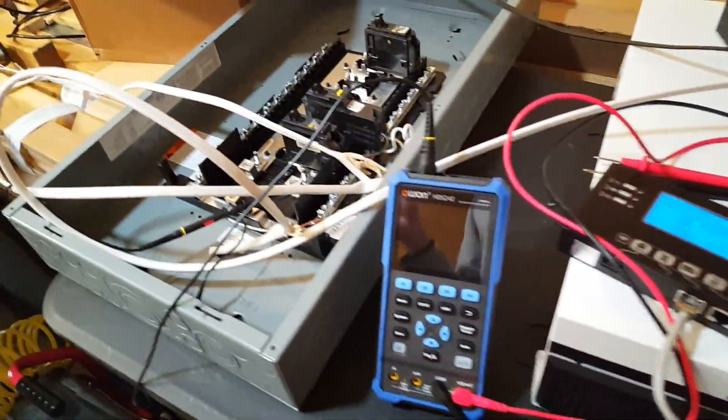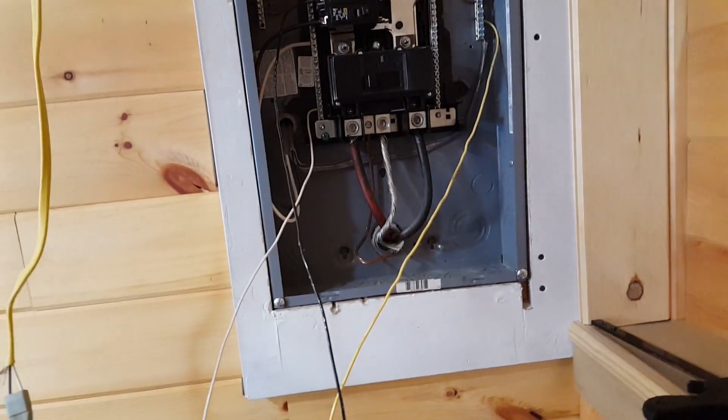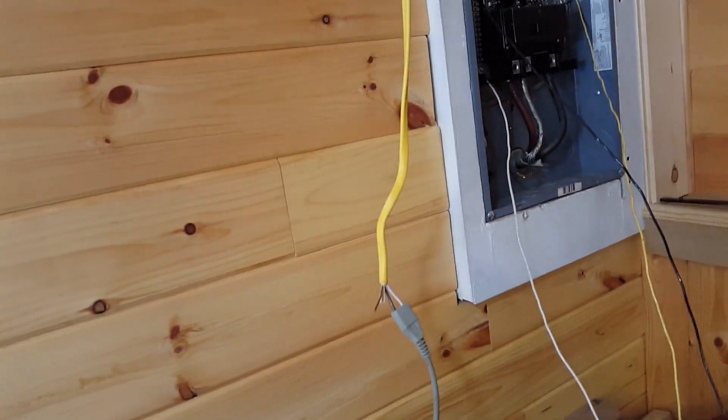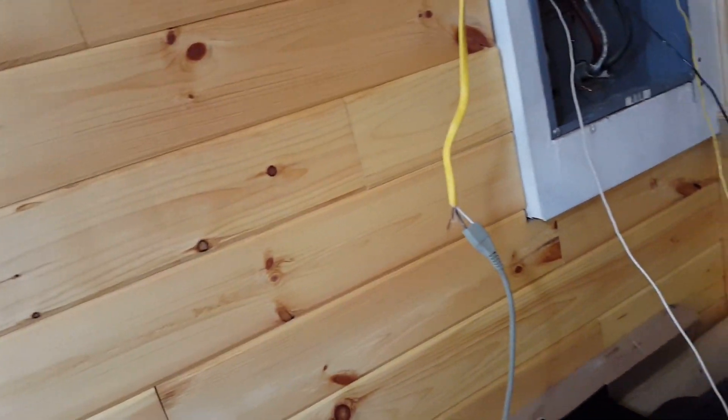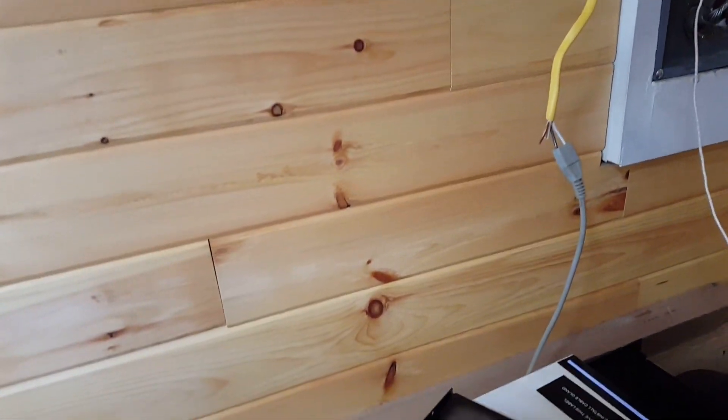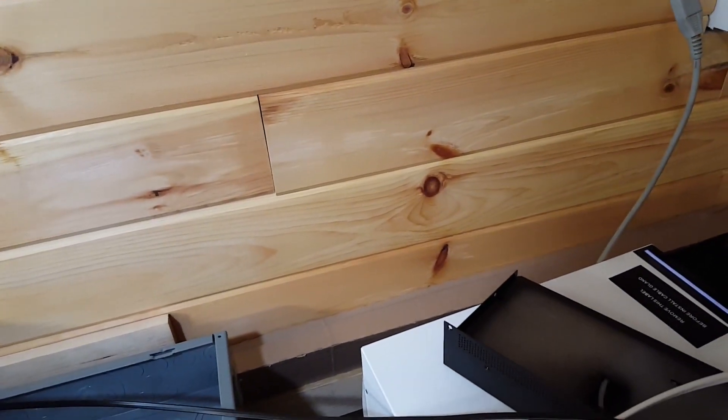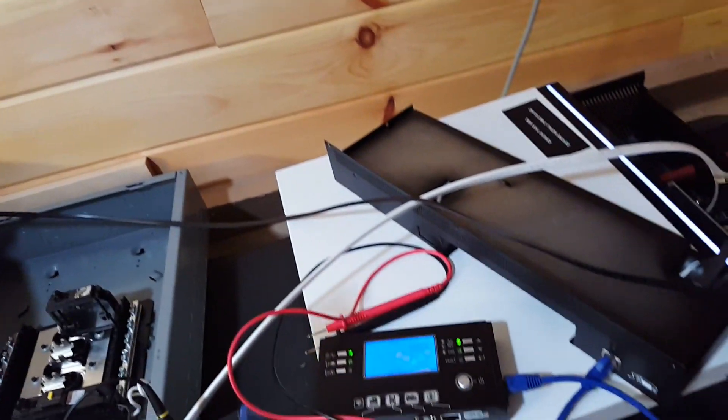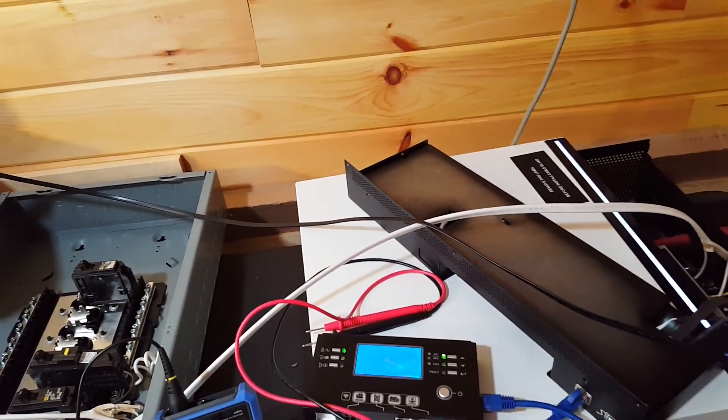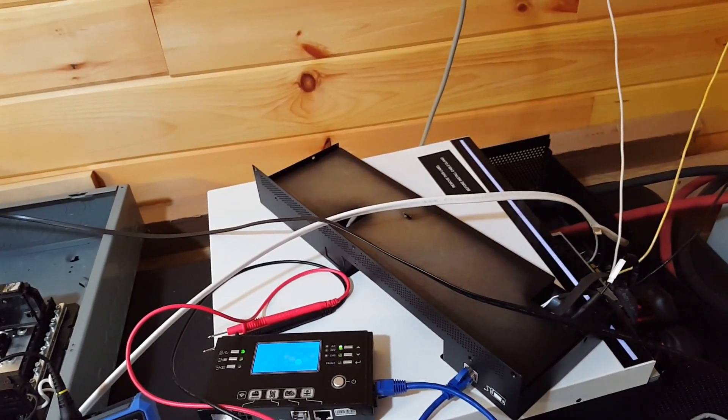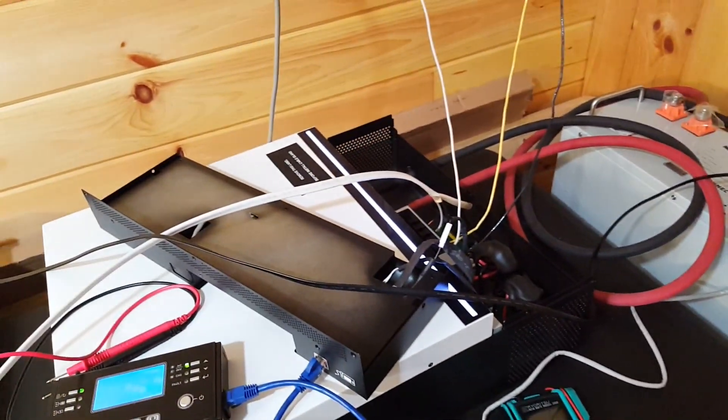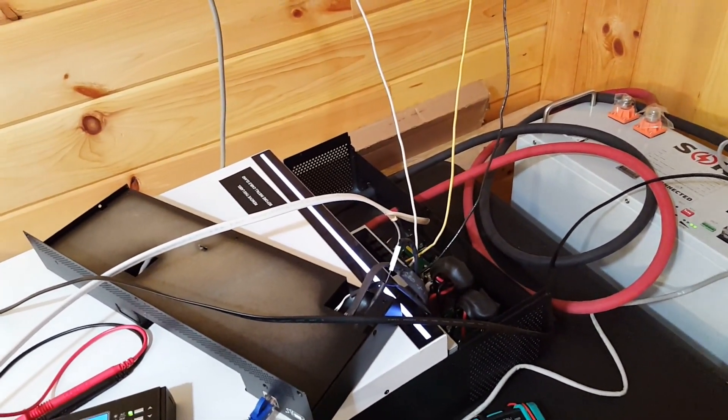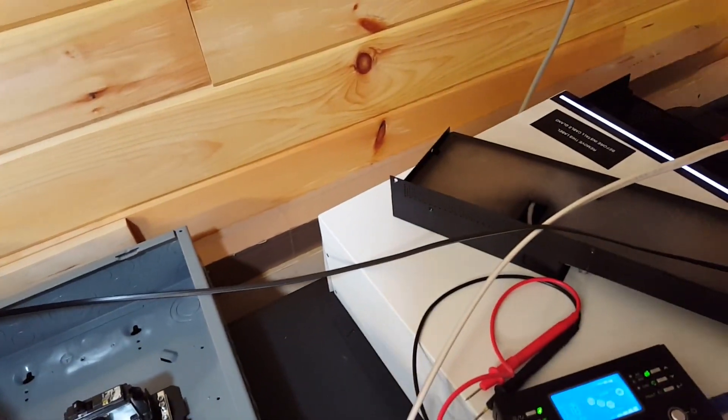I've repeated this enough times at this point. You can clearly see it. It will not sustain 34.5 amps on the AC side, 4,100 watts of load on the AC side. That puts 4,500 watts on the battery with the 10% inverter efficiency losses. The battery will kick into OCP. Okay. At 4,500 watts. Now, 4,500 watts at the voltage of 50 volts. You take 4,500 divided by 50, that's 90. It's OCPing at 90 amps DC on the DC side of the battery. It's not doing 100, man. It's not doing 100. 90 is not 100.